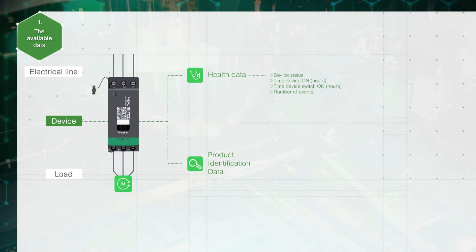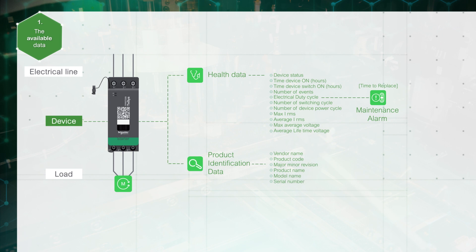At the device level, product identification and health data are available: time device on from the beginning, time device switch-on, tracking the time the motor has been engaged, and number of events — which can help in preventive maintenance and diagnostics. A maintenance alarm is triggered, for instance, when ninety percent of the duty cycle is exceeded. Health data and product identification data are useful for diagnostics and preventive maintenance planning.